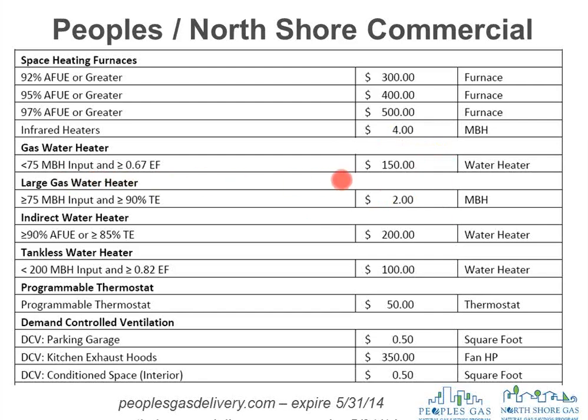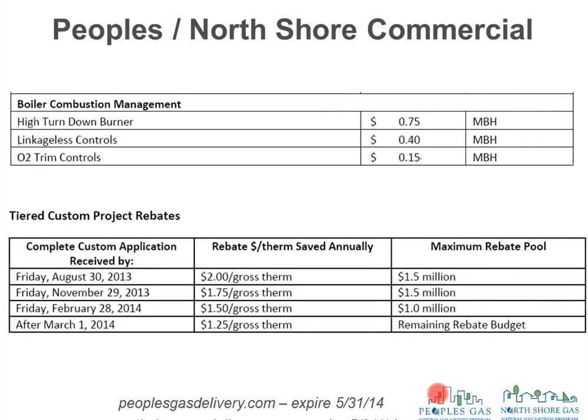There are rebates for small gas water heaters, $150. There are rebates for larger ones. It's $2 per MBH. Indirect water heaters are on the program. So if you add a tank onto an indirect system, it's $200. If you're doing it on a big system like a domestic water on a condo building, you're probably going to take the custom route instead of this route because that's just the tank, and you need to get the boiler rebate also. Tankless is on here. Programmable stats, $50. The DCV stuff that I just mentioned a minute ago is all on here. There are now rebates on the prescriptive standard side for burner combustion management control. So if you want to put linkageless control in there or something like that, there are rebates available for that. And then the other big change is on the custom side.